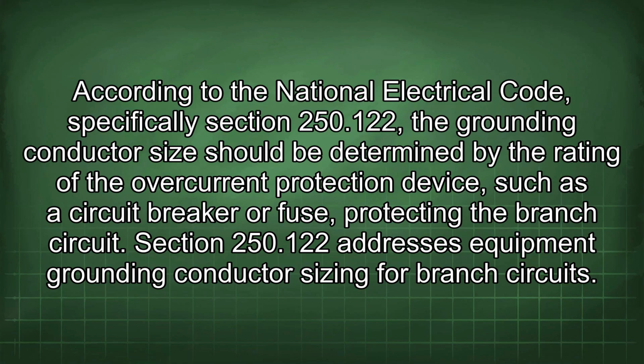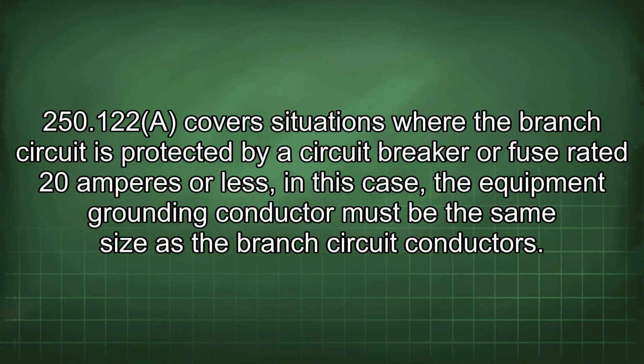According to the National Electrical Code, specifically Section 250.122, the grounding conductor size should be determined by the rating of the overcurrent protection device, such as a circuit breaker or fuse, protecting the branch circuit. Section 250.122 addresses equipment grounding conductor sizing for branch circuits. 250.122 covers situations where the branch circuit is protected by a circuit breaker or fuse rated 20 amperes or less. In this case, the equipment grounding conductor must be the same size as the branch circuit conductors.